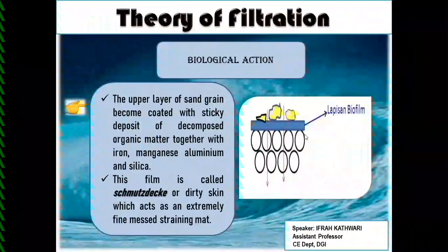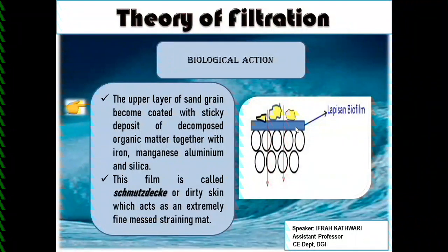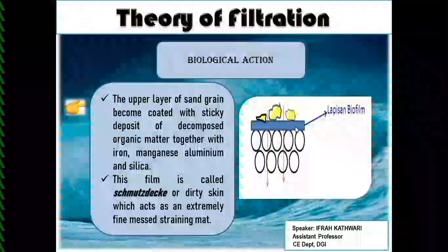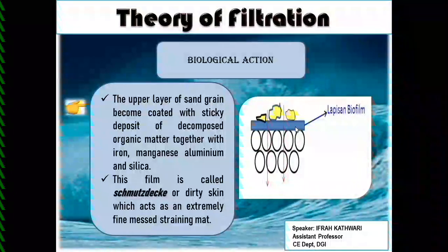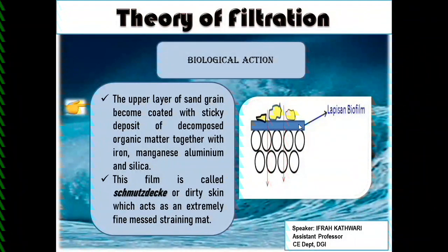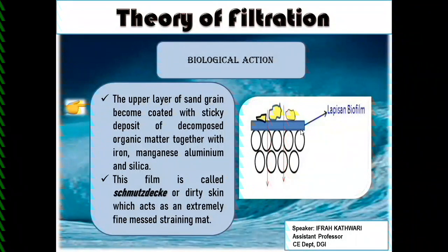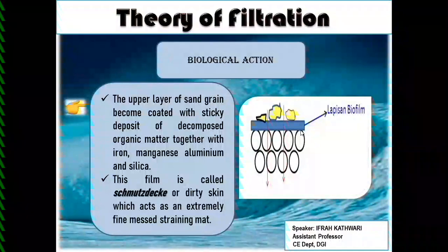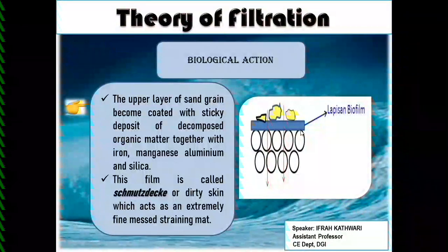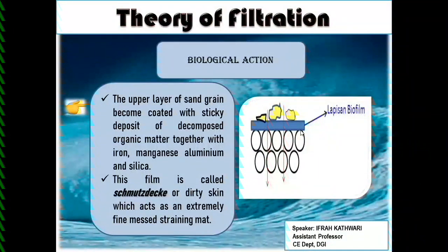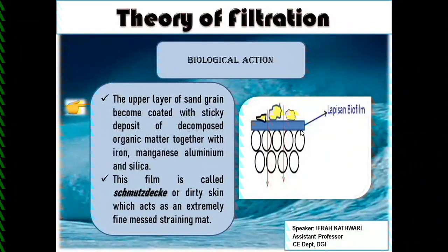After that, we have biological action. The decomposed organic matter that can be present in water may get deposited over the layer of sand, or over the sand particles. Whenever it gets deposited, it forms a layer, and that layer is known as dirty skin, or dirty film. This organic matter, along with iron, manganese, aluminium, silica, forms a thick film known as dirty skin.